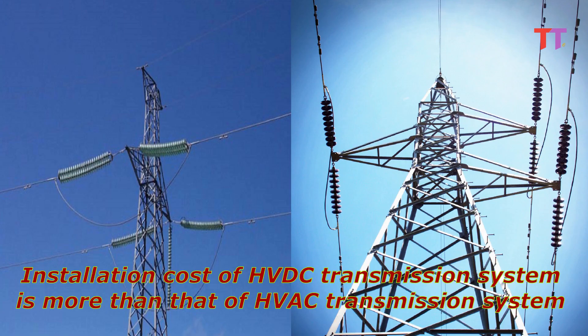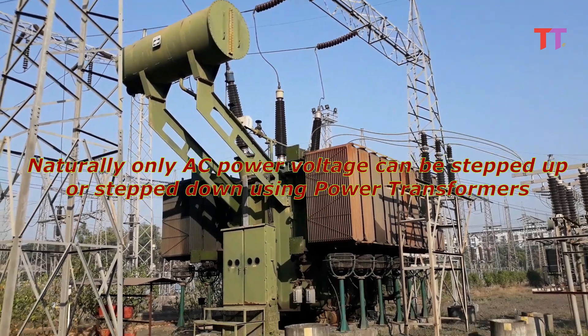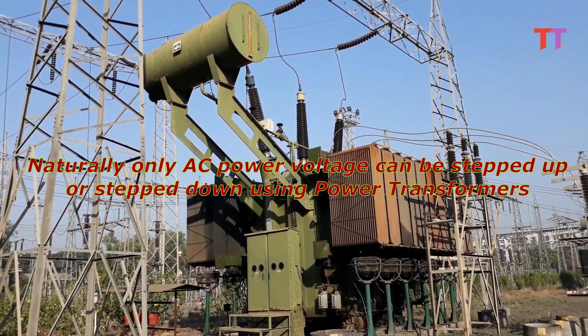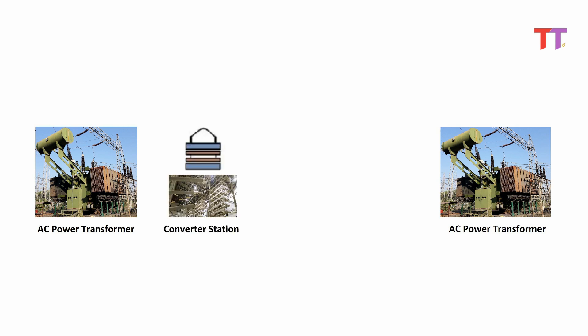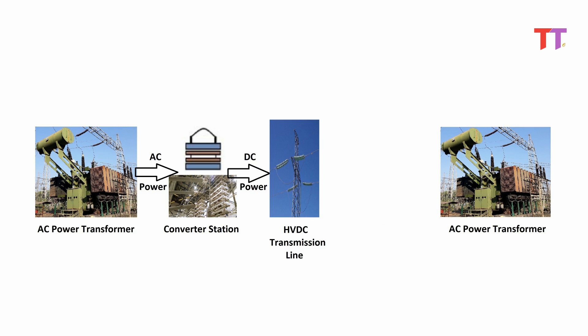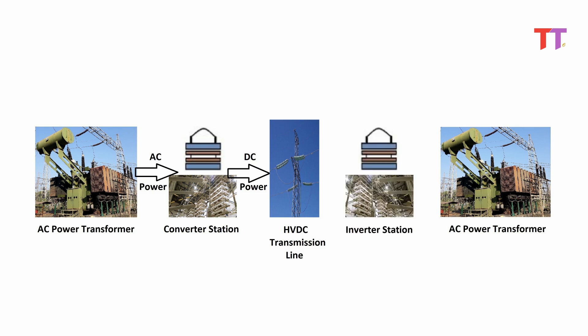Capital cost: Installation cost of HVDC transmission system is more than that of HVAC transmission system, because naturally only AC power voltage can be stepped up or stepped down using power transformers. Hence for HVDC transmission, we have normal HVAC power transformers at both ends. Then there is a converter station at the sending end which converts stepped-up AC power into DC power. This DC power is transmitted over distance by DC transmission lines. At the receiving end, there is an inverter station which converts DC power back into AC power, which can again be stepped up or stepped down using power transformers. These converter and inverter stations increase the capital cost of HVDC power system compared to HVAC.